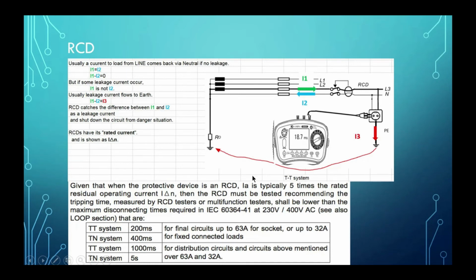what will happen? People go and touch this one. People touch the unsafe equipment. People will get burned. Okay, so it is important for the RCD to trip, to prevent the human from electric shock. Okay, understand? And in our instruments, we test the tripping time.